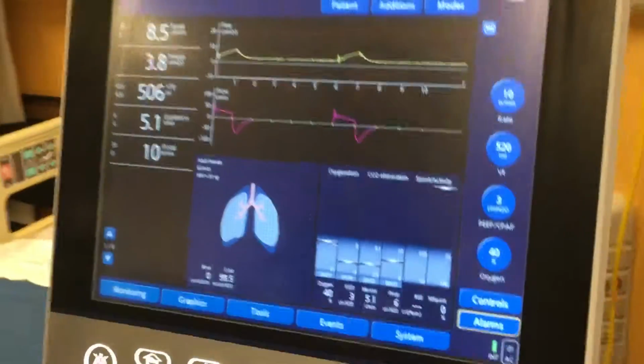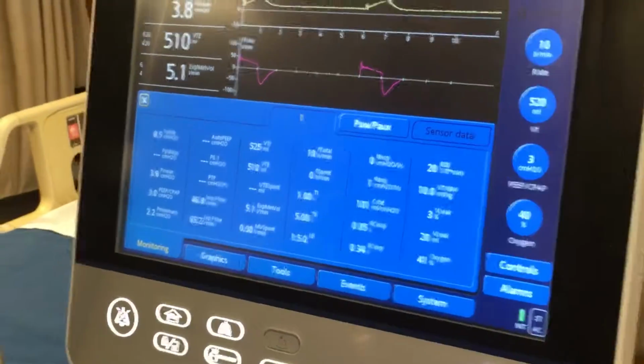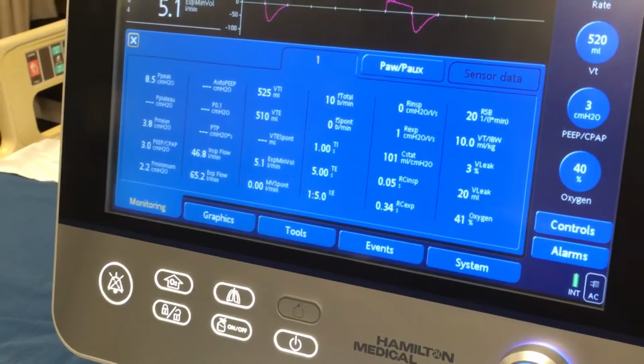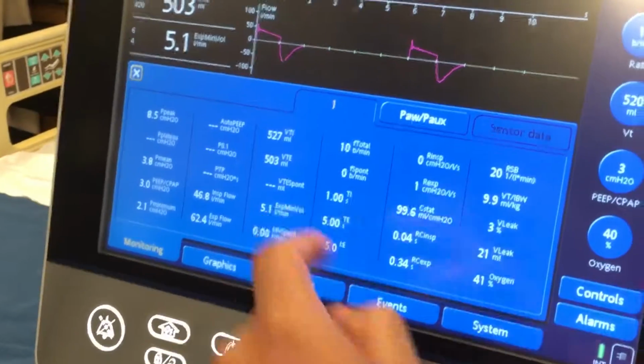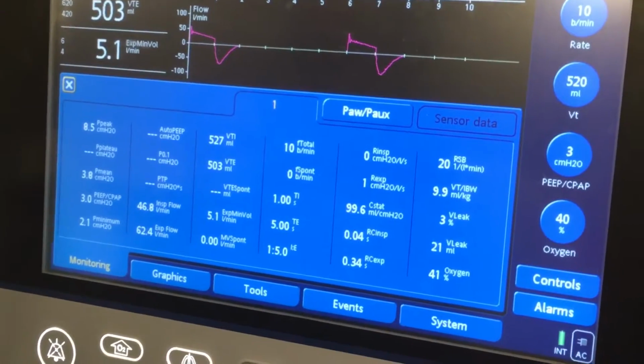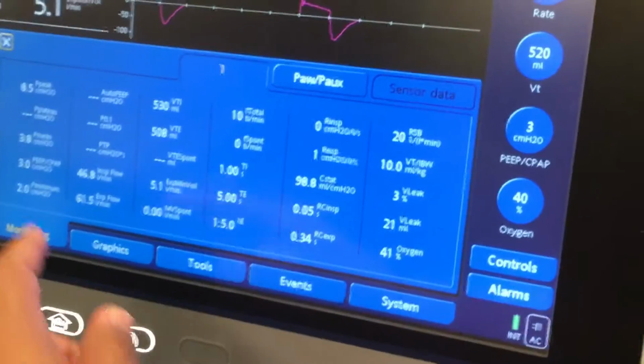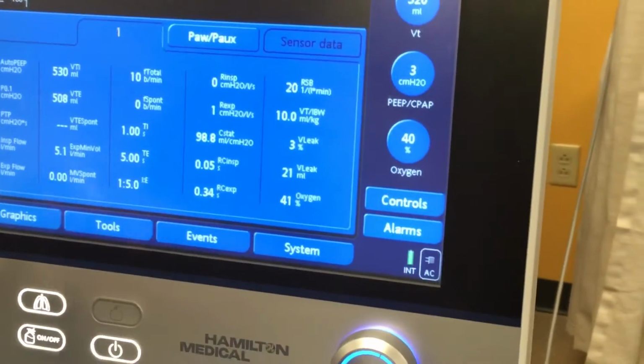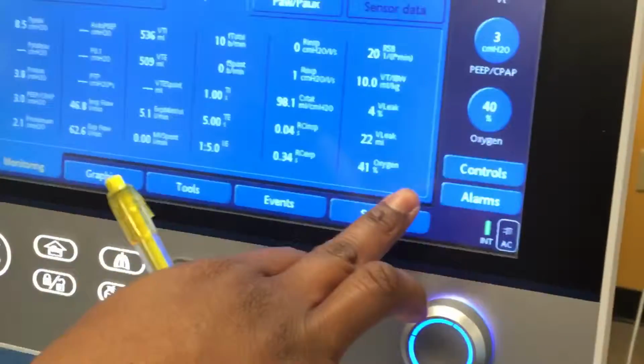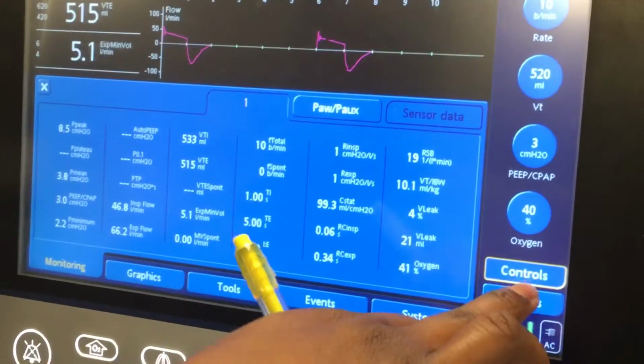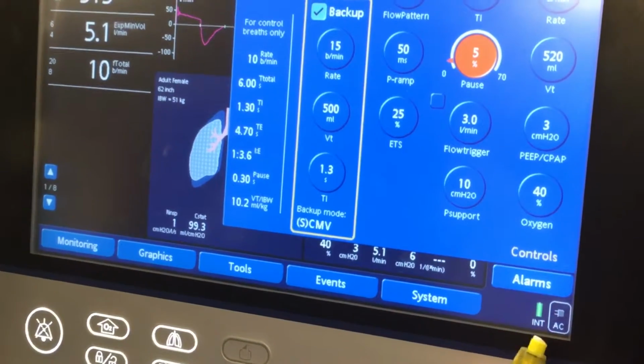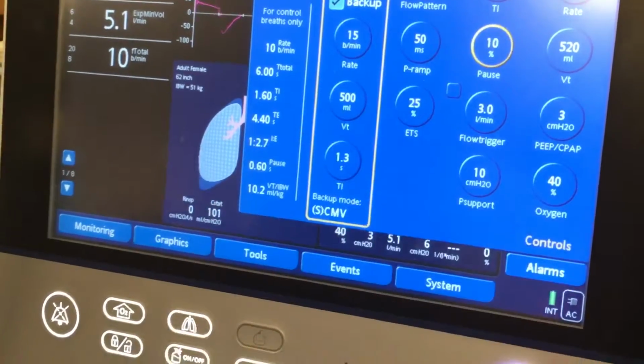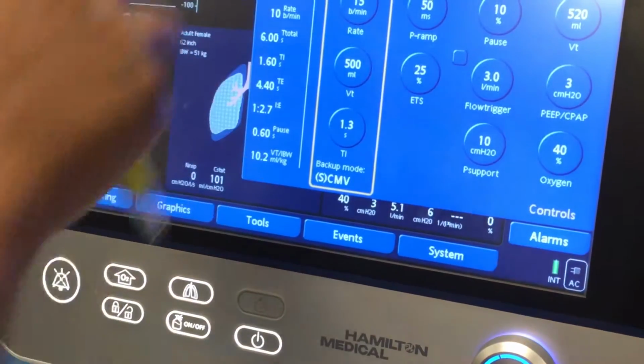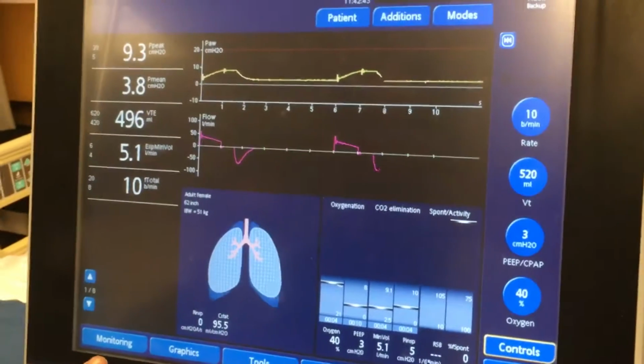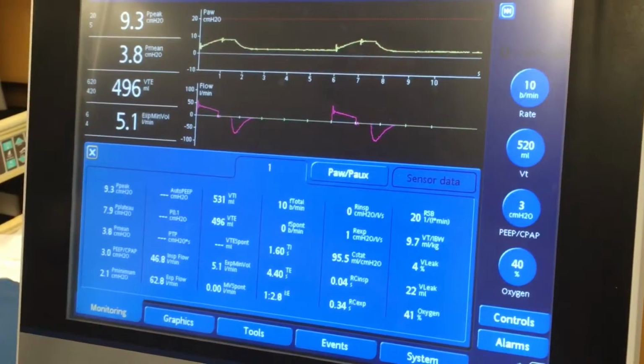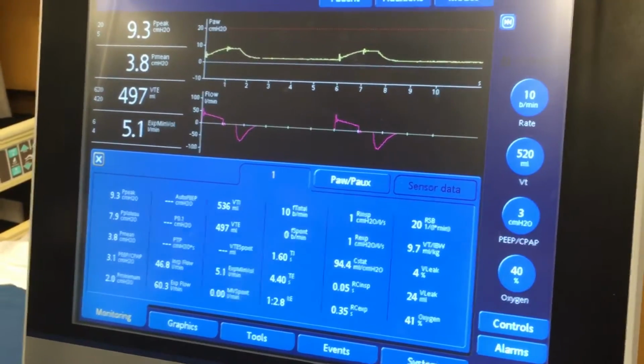Technically with this one, we can go to monitoring, and it gives us a lot of the values. The expiratory minute volume is right here, 5.1. The peak is 8.5, and then the plateau, we can do the percent. Hit it and X to see what it's going to be. There it is, 7.9. Okay. Cool.